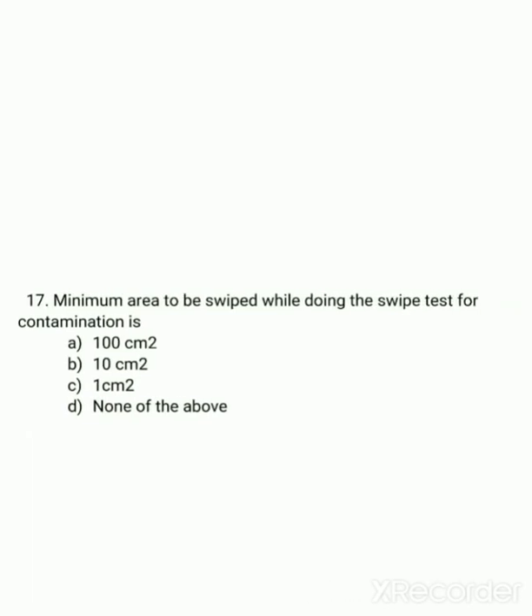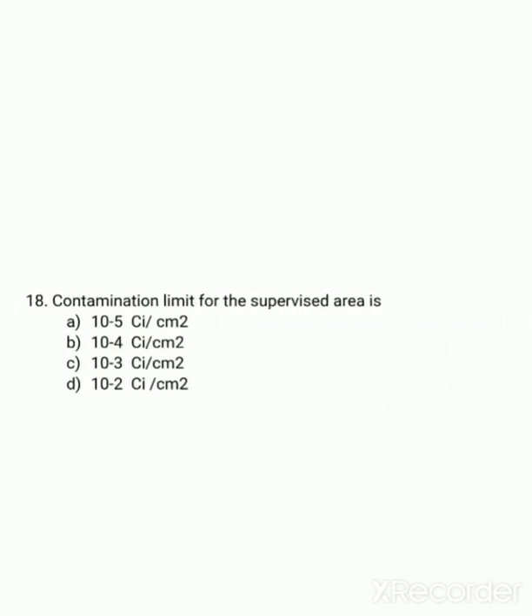The minimum area to be swiped while doing a swipe test for contamination: we know it is 10 cm × 10 cm, that is 100 centimeter squared. So the exact answer is A — 100 centimeter squared.